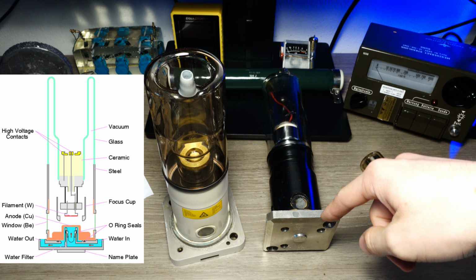So the physical mechanism in which this type of tube works differs between the medical one here and this other X-ray diffraction tube, because in the medical tube you have a tungsten anode, and you usually apply a voltage of around 60 kilovolt to 120, but hundreds of kilovolts are applied to, for example, tomography X-ray machines that use really high energy, while this lower and smaller tube usually uses up to 60-70 kilovolt, and because of this the voltage is not enough to excite the characteristic transition of copper, so you only get a Bremsstrahlung emission from this type of tube.